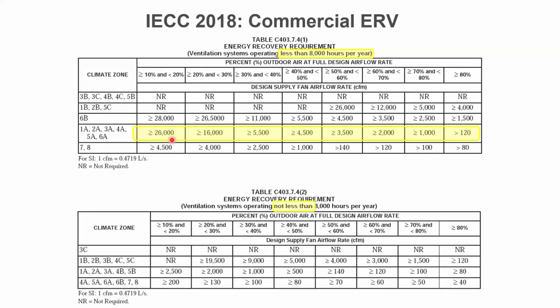But if I go to systems that operate most of the time, right, most of the time meaning like hospitals, Walgreens, the BP gas station or something like that, right? They're never closed really. Those people are going to have to do ERVs pretty much every project unless they have less than 10% ventilation air. And some of them may, but most of them probably don't. So they're probably going to have to do an ERV for just about everything in those cases.